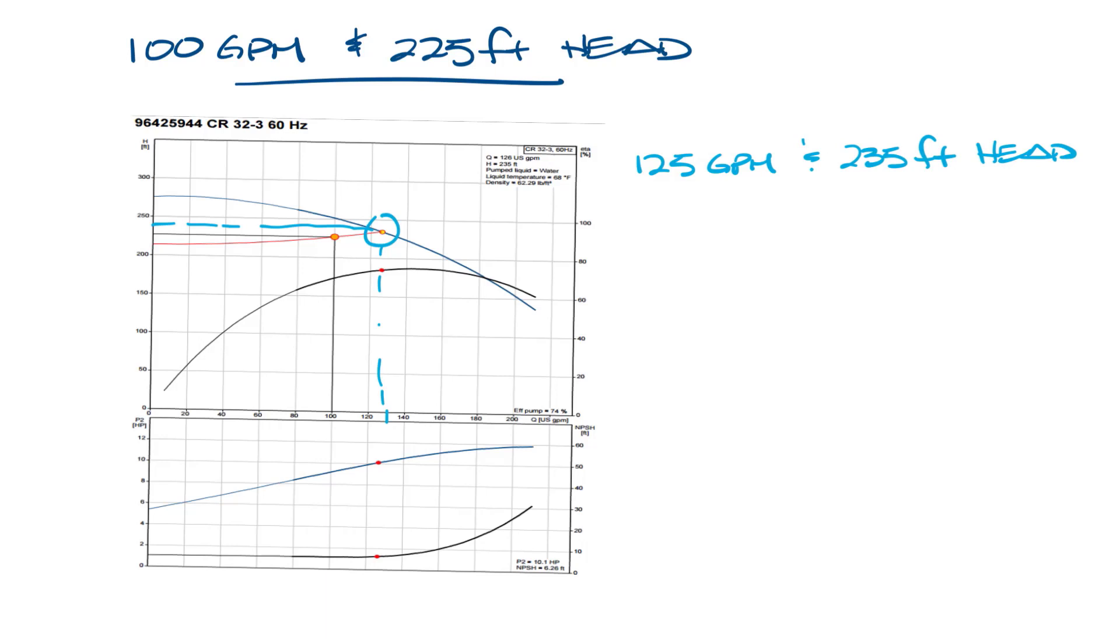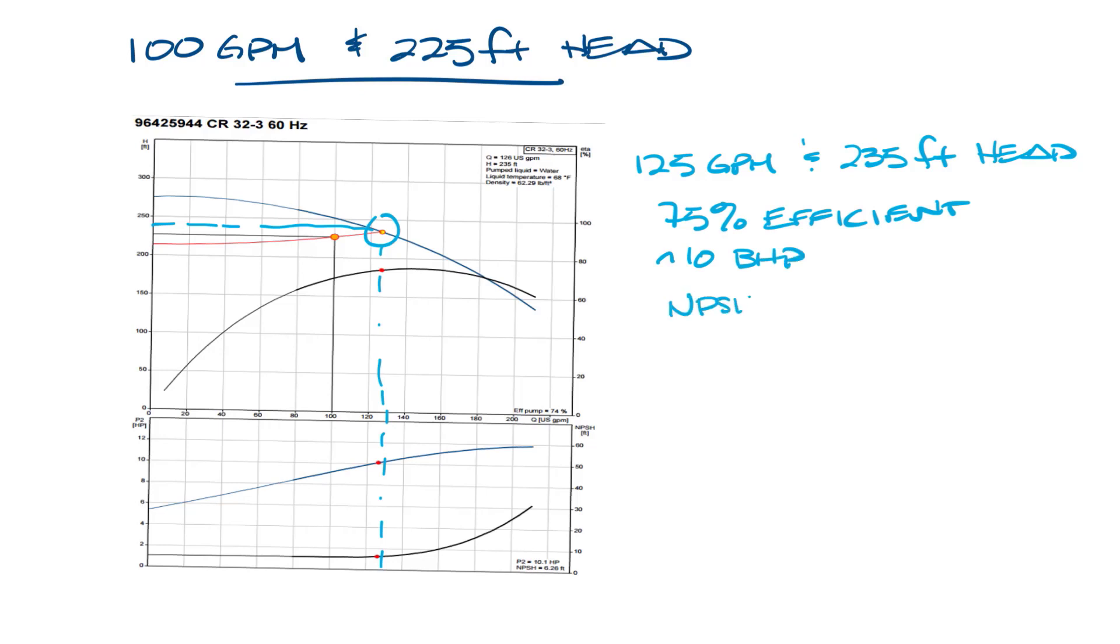If we follow the operating point down, it's about 75% efficient, and the brake horsepower is about 10 horsepower, and the NPSHR is around 6 feet, or you can see in the corner it says 74%, 10.1 horsepower, and 6.26 feet.